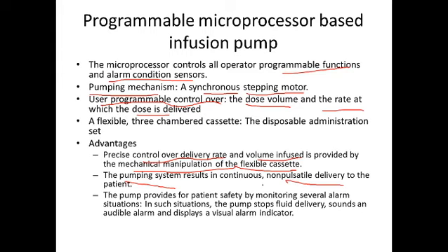Okay, and the third thing is the pump provides patient safety by monitoring several alarm situations. In such situations, the pump stops fluid delivery. So what will happen? Whenever there is an alarm situation, the pump will stop fluid delivery and it sounds an audible alarm, and it also displays a visual alarm indicator. Those things also you can implement in this infusion pump. So if there is any critical condition, it will not only stop the fluid delivery, but it will also sound the audible alarm there.